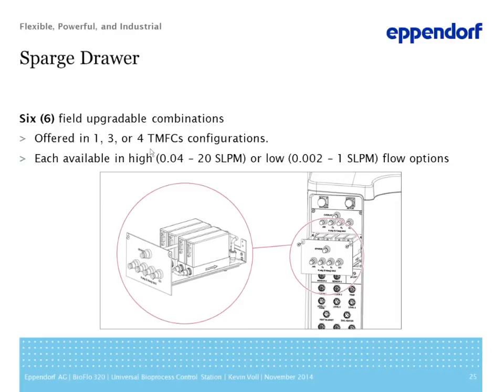Two screws are removed, the drawer is pulled out of the control station, a new drawer is added. Because we use digital thermal mass flow controllers, the system detects the drawer that's added and automatically configures the software to the drawer that has been installed. So again, this can be done, and I've done it myself, this can be done in under 5 minutes. So the ability to change the control abilities of a system in under 5 minutes is really new for us, and it's really new to the market.